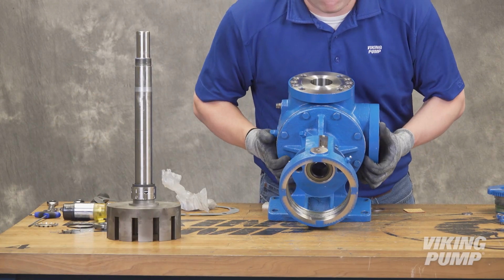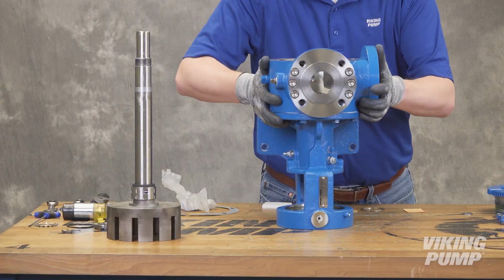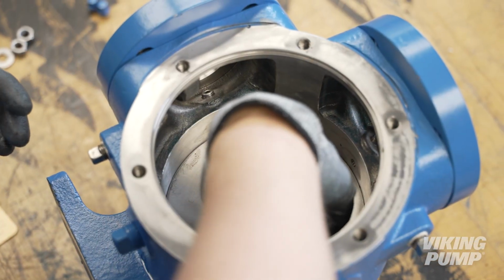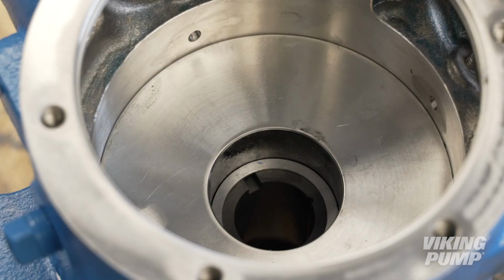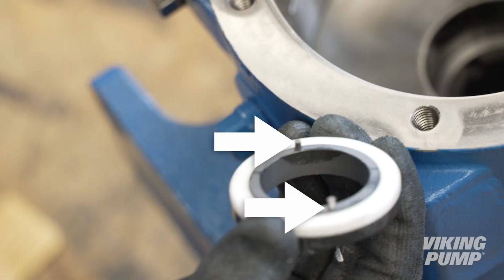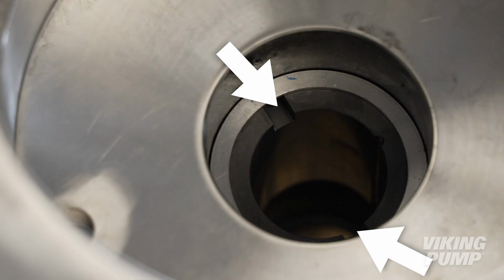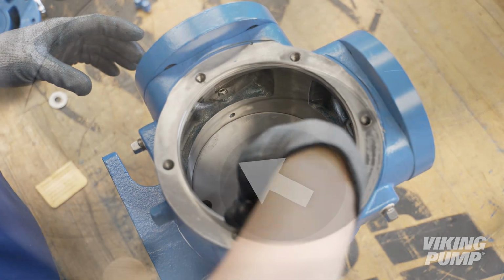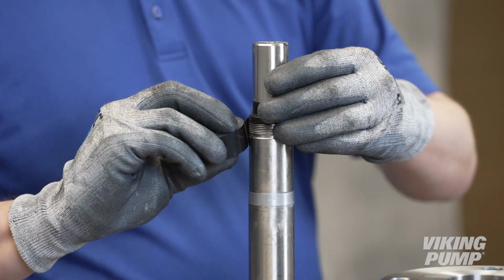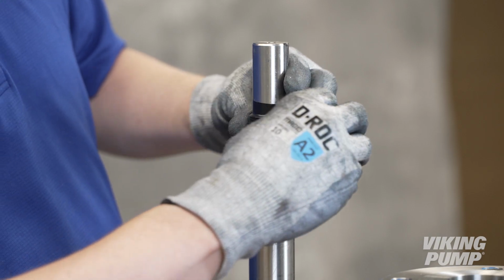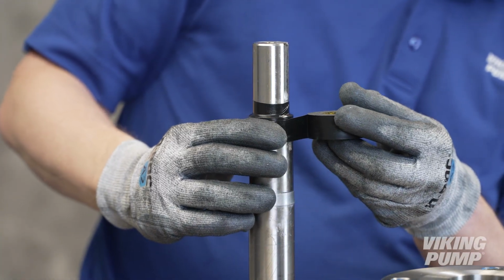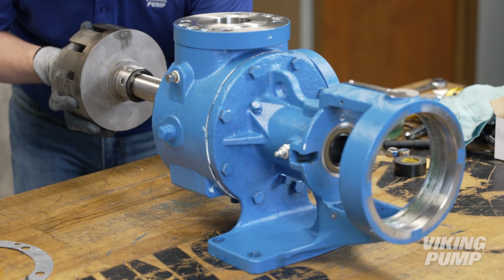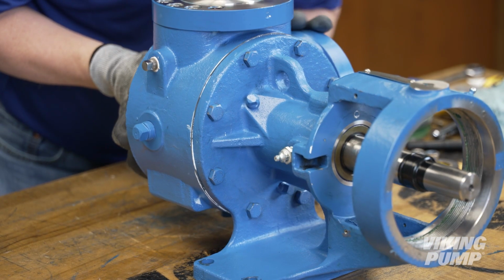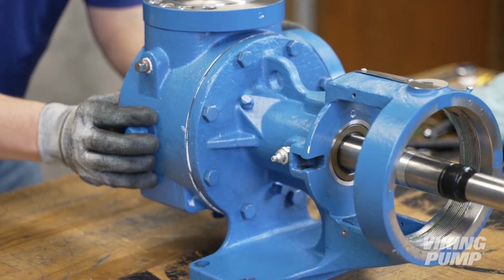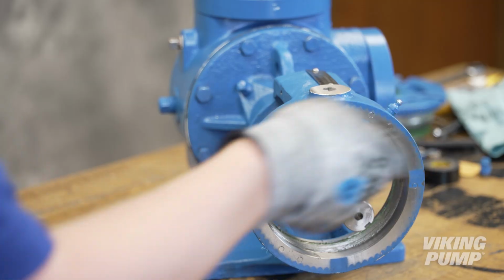Turn the pump up onto the bracket to aid with seal seat installation. First, install the seal spacer. Next, install the seal seat with the pins down and aligned with the grooves in the bushing. Carefully push the seal until it is fully seated against the seal spacer. Before installing the rotor shaft, tape the threads at the end of the shaft to prevent damage to the lip seal in the bracket. Lubricate and install the rotor shaft. Take care not to damage the seal seat or lip seal during installation. Remove the tape and seal installation sleeve.